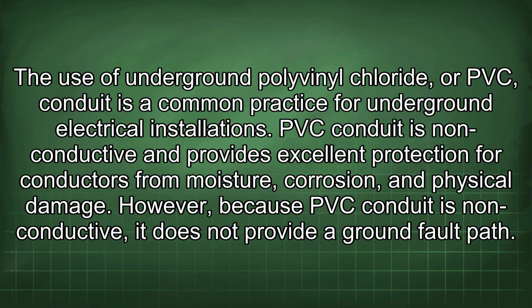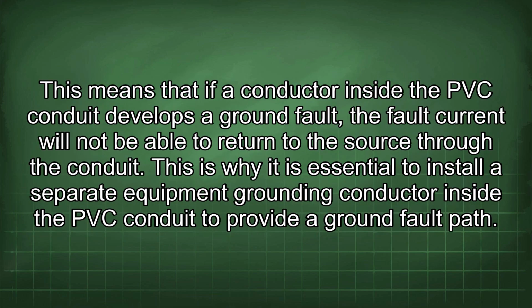The use of underground polyvinyl chloride, or PVC, conduit is a common practice for underground electrical installations. PVC conduit is non-conductive and provides excellent protection for conductors from moisture, corrosion, and physical damage. However, because PVC conduit is non-conductive, it does not provide a ground fault path. This means that if a conductor inside the PVC conduit develops a ground fault, the fault current will not be able to return to the source through the conduit.